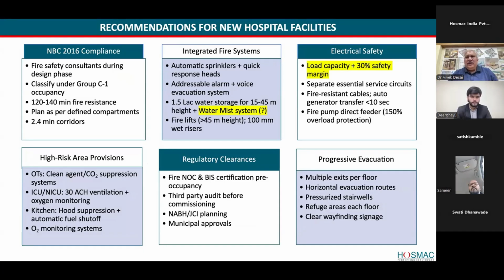And like in the electrical safety, the yellow point is 30%. He mentioned the 20% safety margin. What the standard says globally is a 30% safety margin. Now, this is something where the client needs to be educated. They generally don't like to do that because it's a cost factor for them, right? But fire resistant cables are important, like he explained to you. So all of those are things which one should follow very strictly. Okay.